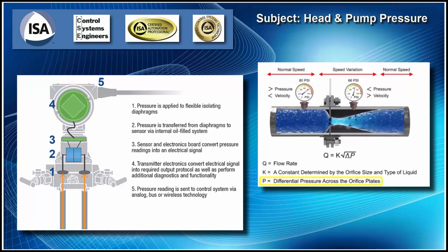So you say, well, if you're going up a column of water, you're losing work. You said it's lighter at the top than it was at the bottom. Well, Pascal's law of hydraulics says that in a closed system that's pressurized, the pressure is the same everywhere in the closed system. So if we follow this tube from the transmitter down into the pressure pipe, the process pipe, that's a closed system. Now, it's divided by a work drop or a pressure drop across the orifice.